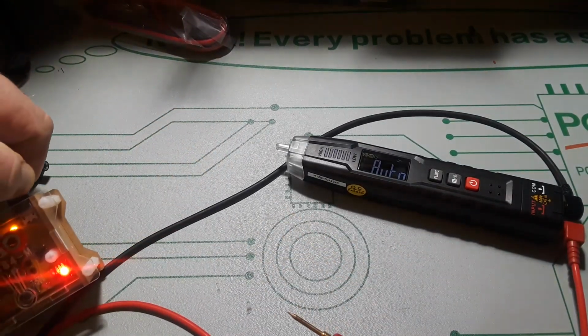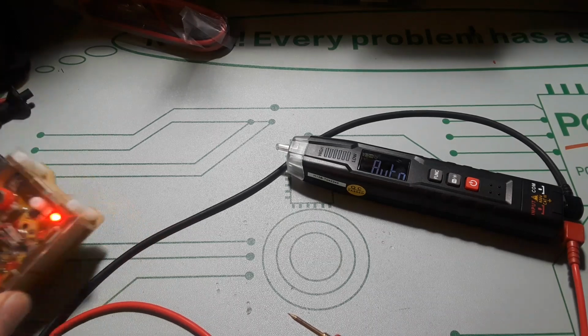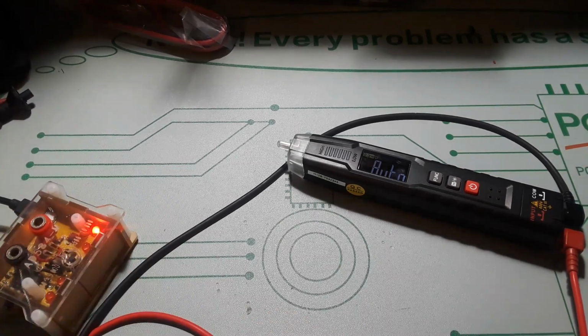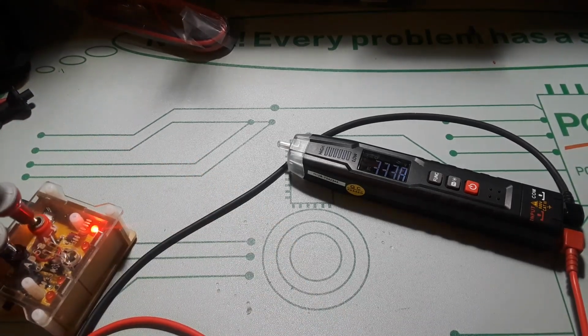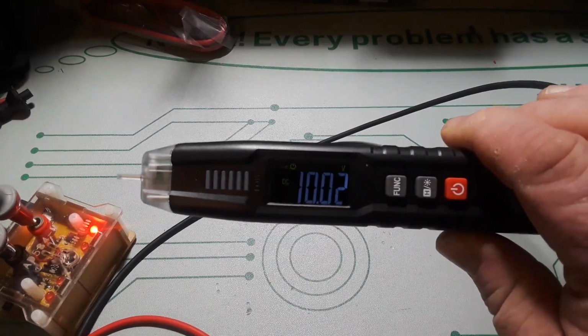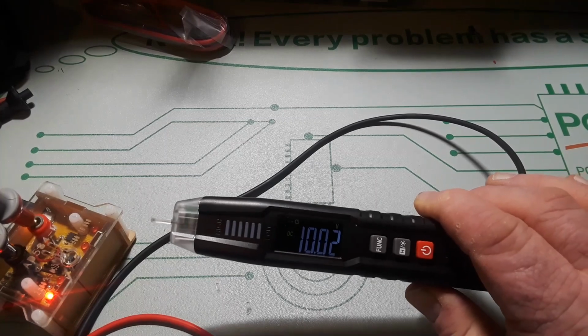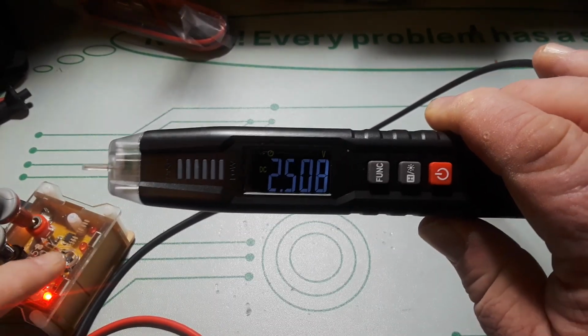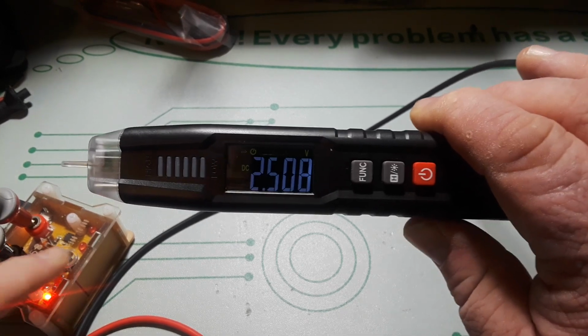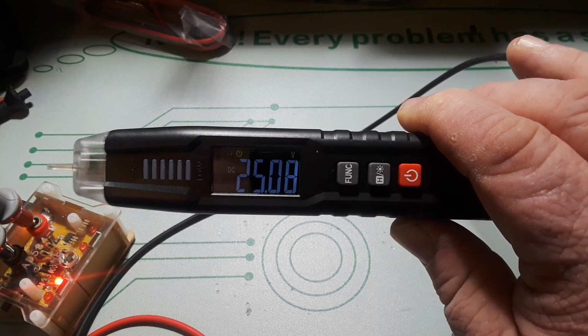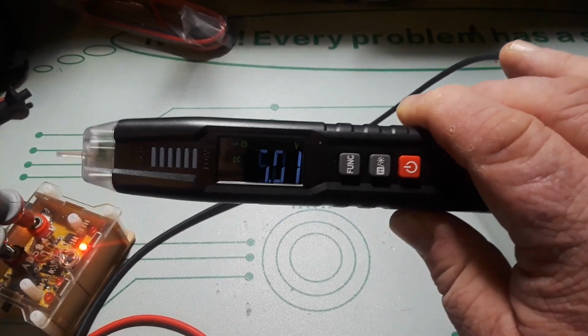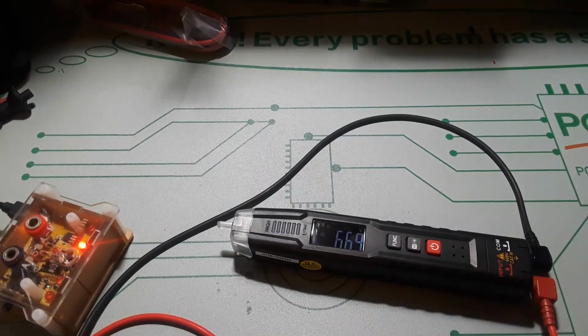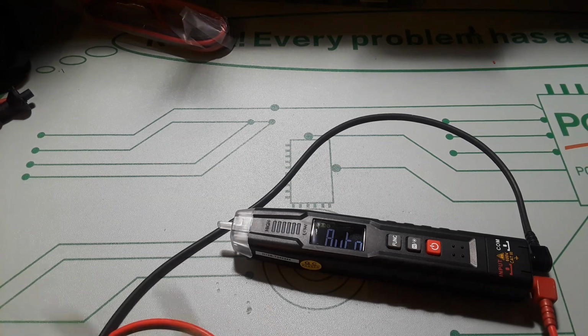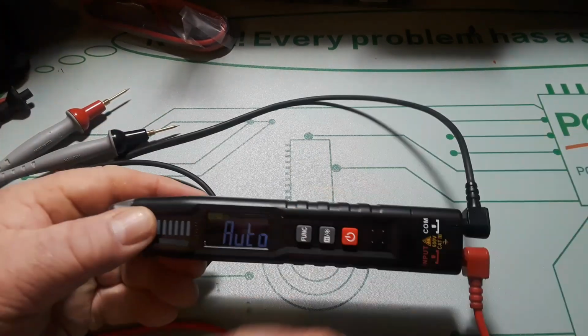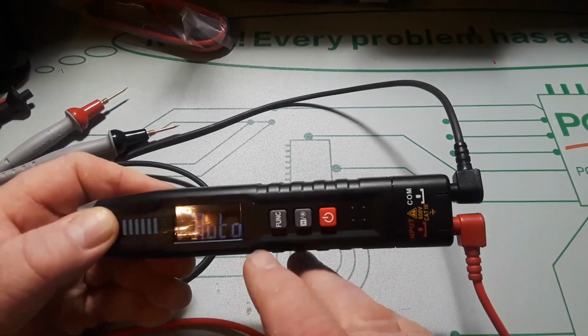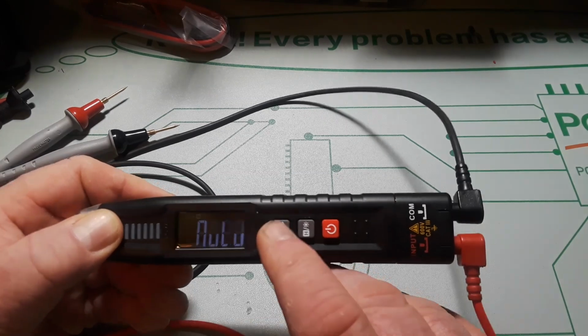All right, let's bring in the AD584M voltage tester, which is currently set for 10 volts. And we get 10.02, 2.5 volts, 2.508, 5 volts, 5.01, and 7.5 volts, 7.51. So, you know, these days with multimeters, there's really no trouble with them reading. It's accurate enough. Everything's digital. Let's try the function button again.